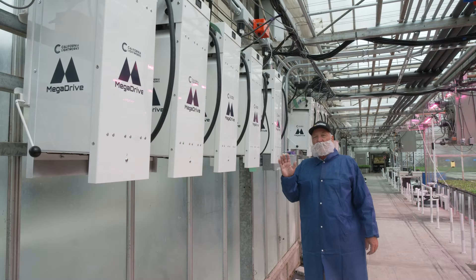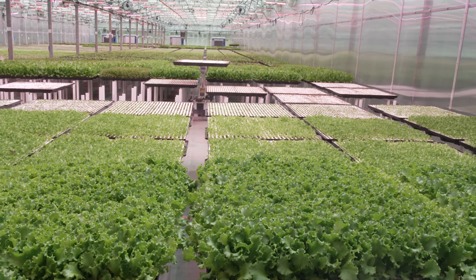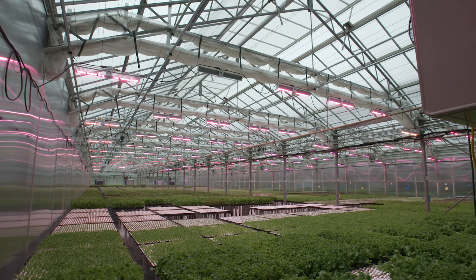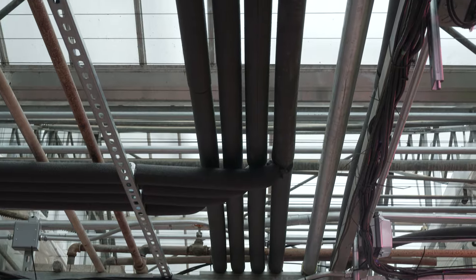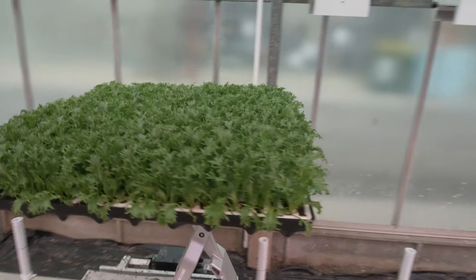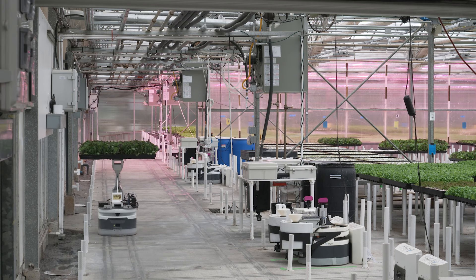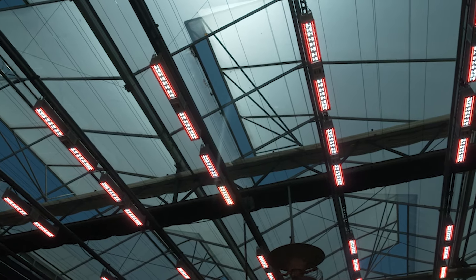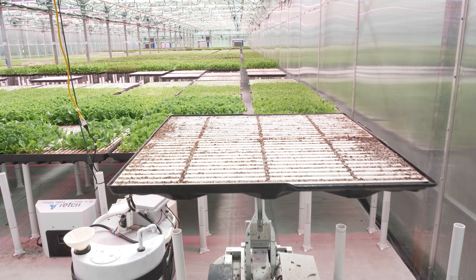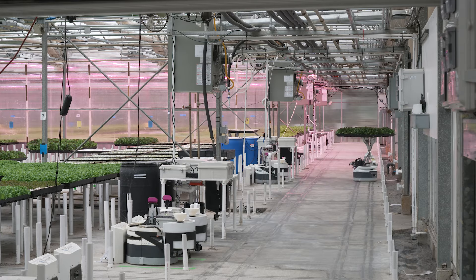With every Mega Drive system, the drivers and power supplies are separate from the light fixture. You get the heat out of the canopy area, and installation is much simpler because there's no wiring over the canopy at all — the only electrical wiring is to connect power to the power supplies. These can be mounted as much as 300 to 400 feet away from the canopy, out in an aisle or in a room, making this very easy to install, monitor, and maintain. Spectrum is controlled through the power line, so there are no problematic wireless controls or additional data cables — it's all controlled through the power supplies, and the system can automatically adjust light levels depending on the availability of natural sunlight.